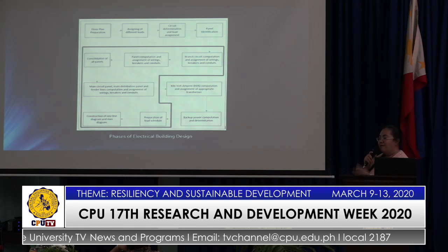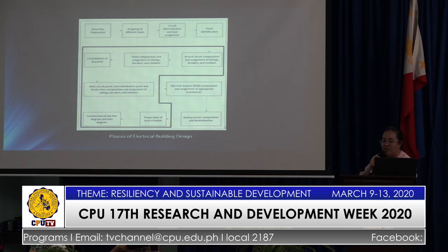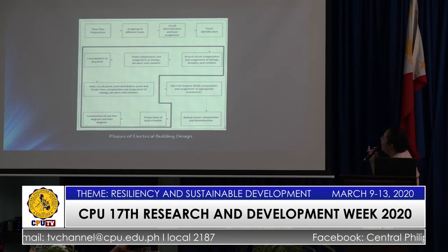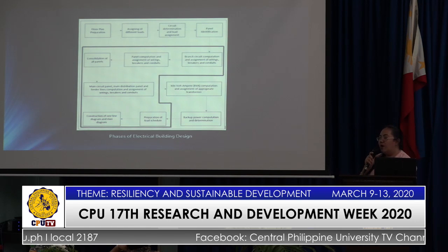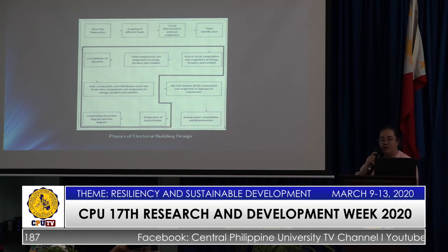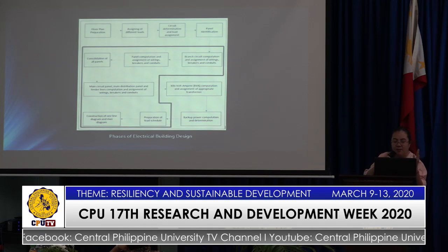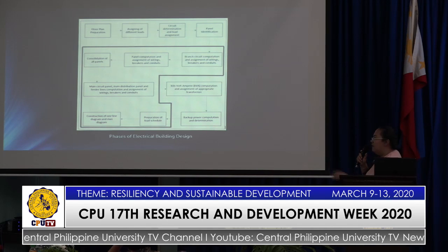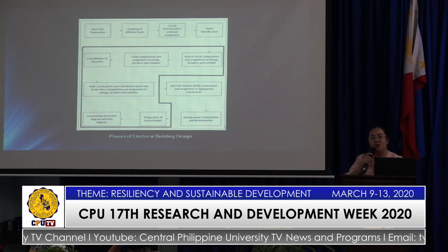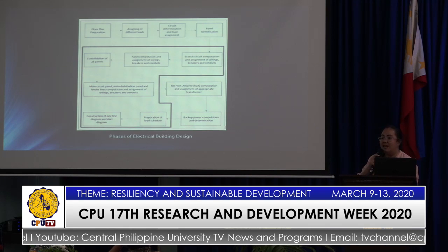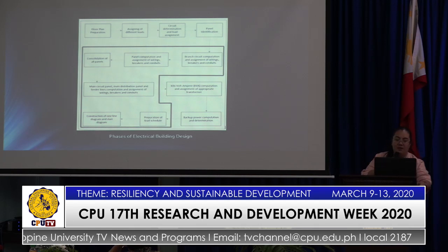Now, if I already have the assignments of load and I already have identified my panels, it is the time that I do my computation. This is the time wherein I compute for the branch circuit ampacity, what circuit breaker I should use, what wires I should use, and what conduit I should use. And of course, panel computation of all panels, and then of course, at the end, the preparation of the load schedule. Basically, the load schedule is just a summary of my design analysis. So before that, let me show you what I mean kanina.